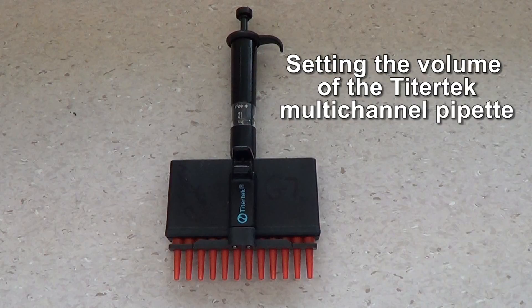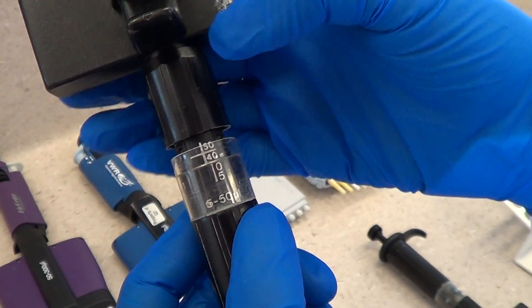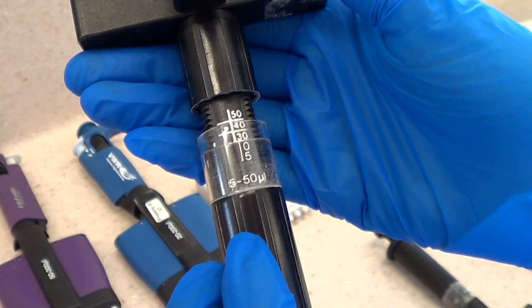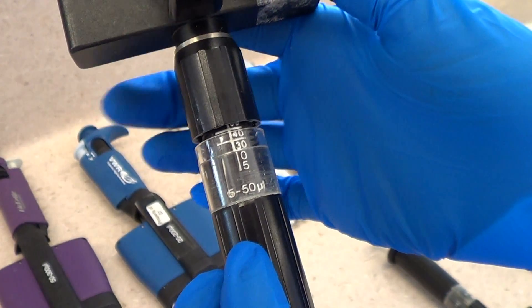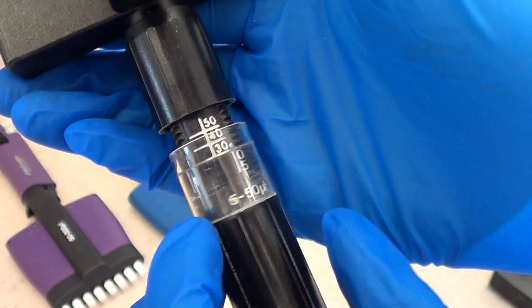Setting the volume of the Titertek multichannel pipette. Loosen the top section, then screw or unscrew the lower section until the edge lines up with the required volume. Then tighten the top section. This pipette is set to 30 microliters. Note that each full turn decreases or increases the volume by 5 microliters.